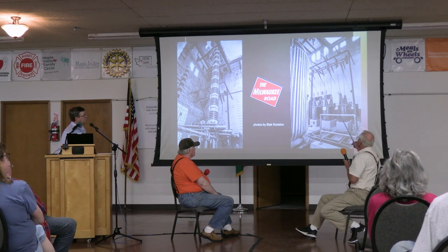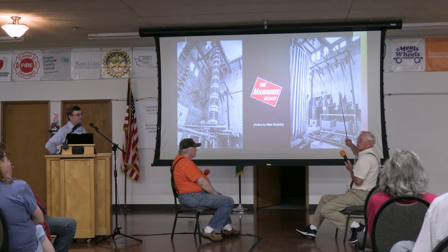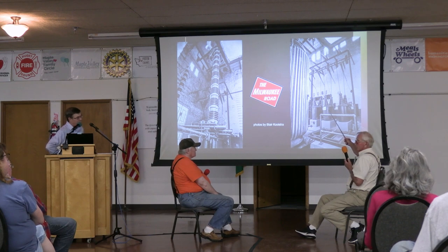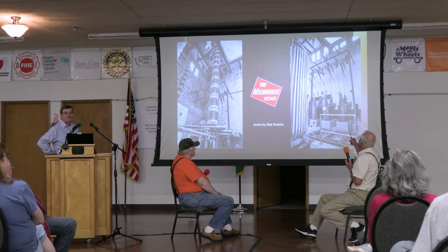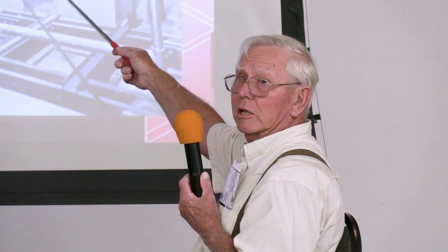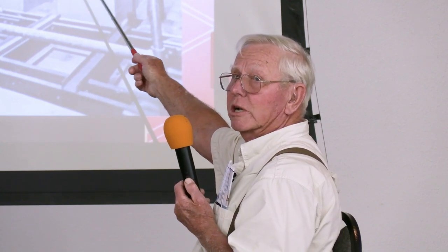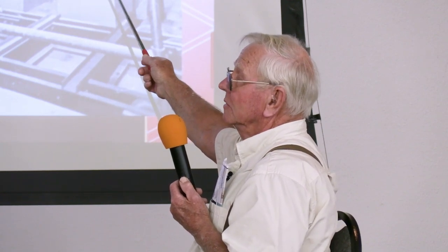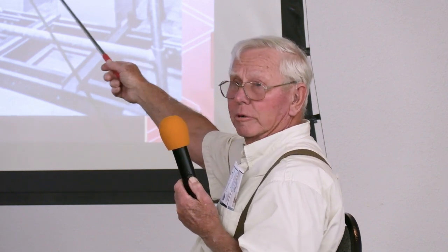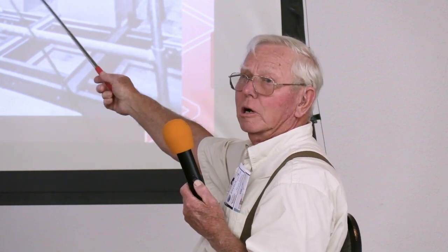And these cans were filled with what's called transformer oil. And every so often, yearly, or kind of dependent probably on operations, you had to drain the oil out of here and filter it, run it through press filters, to get any carbon out of the oil, because if it got too much carbon in it, then it could go to ground and blow a hole right through the cans.